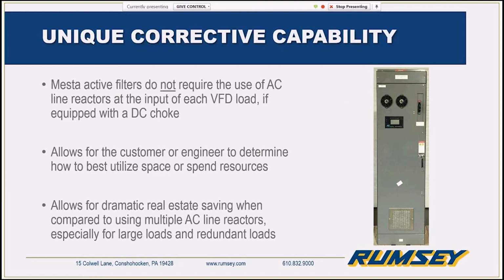I'm sure many of you are familiar with protecting the drives against line transient events, helping if there's oversized transformers, stuff like that. But oftentimes we get called in and we have to meet IEEE-519, and there's only so much space. So we can help to deal with that with less space, because you don't have all those line reactors being used. You normally again see the space savings when you have a large number of VFDs. You normally want to take a look at an active filter if you have 3 or more drives totaling at least 150 horsepower. And we'll talk about that a little more in depth as well.